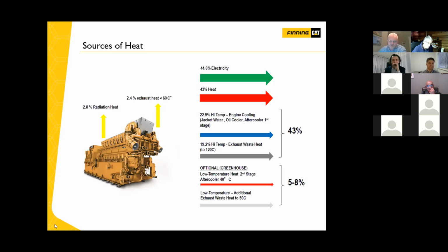So across, I'll just touch on exhaust waste heat. You may notice that exhaust waste heat goes to 120 degrees C, that temperature does vary across applications and components that you're expecting to see in the exhaust stream. Basically, if you extract too much heat, we can condense. That means you're then pushed to using stainless steel equipment. And you also have to deal with the water that you actually produce at that point.